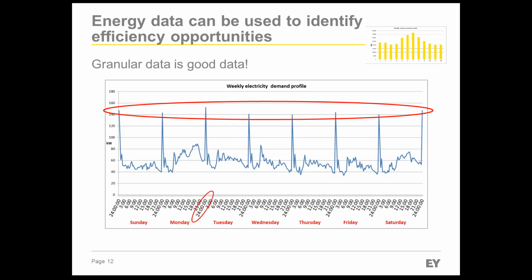So every day, in fact, every night at midnight, there was a spike occurring in the demand profile of this facility. And it was very confusing to us because it's an aged care facility, and we were pretty sure that the residents weren't having a 15-minute party every night at midnight. And so we investigated a little bit further, and what we found was that it went back to the metering that had been installed in the system, and in fact there was a linkage between the metering for this particular facility and one of the neighbouring facilities that was causing this spike.